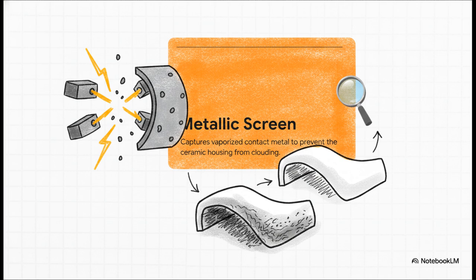Let's talk about that metallic screen. Every single time those contacts pull apart under a heavy load, they draw an electrical arc. That arc is so hot it literally vaporizes a microscopic amount of the contact metal. Without that metallic screen in place, the vaporized metal would just spray all over the inside of the ceramic housing. Over time, that creates a conductive metallic cloud right on the ceramic, ruining your insulation and guaranteeing a catastrophic short circuit.